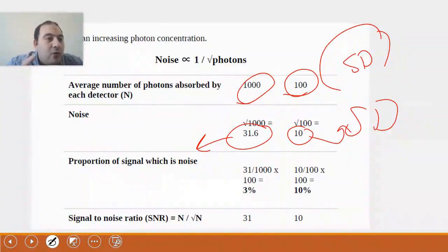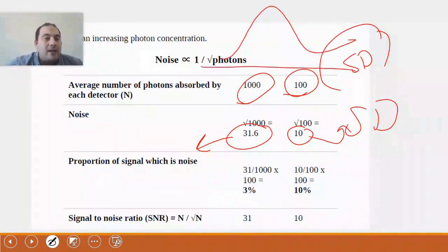You need to pay attention to this point, because when you come to measure using the region of interest, you should know that the value of the standard deviation is not calculated in the same way. This method is the statistical method, which expresses the Gaussian distribution. However, the method the scanner is using is related to its software, which examines every pixel present and starts calculating its variation. It does not take the values as absolute values and work on them with a square root.